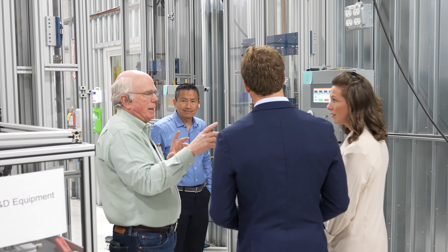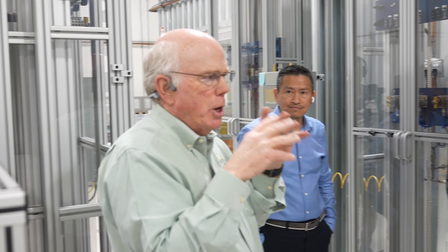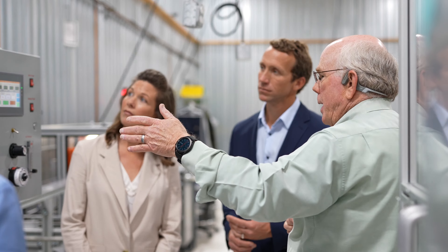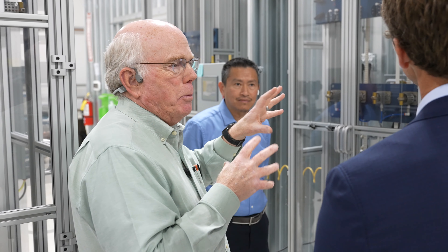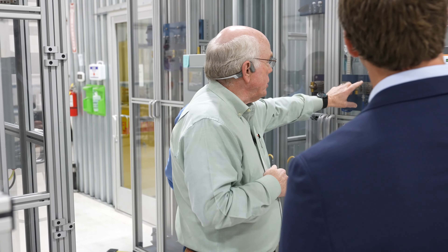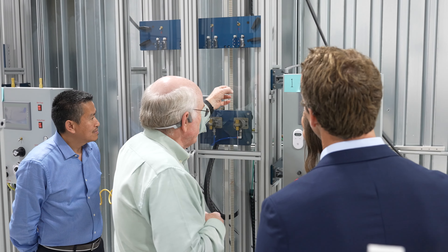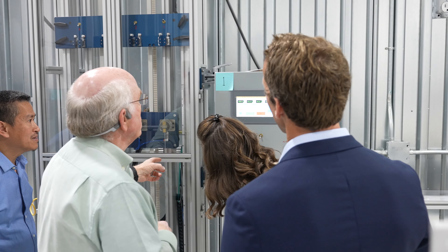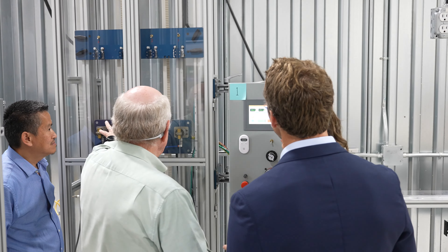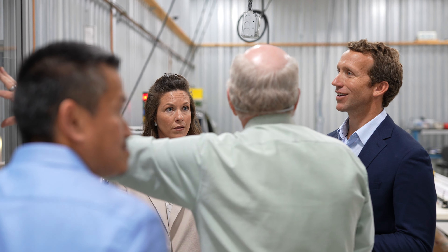The next step in making catheter shafts: after we have the braid onto a shaft with what's called a liner — there's an inner polymer liner, a thin plastic tube — it comes over here and we do a lamination. This can be done in an oven, but we get much better control with this kind of heat process. You see the catheter shaft on a mandrel. This thing travels down — it has four stations and is moving and shrinking because we put a heat shrink layer over this, and this machine is shrinking the layer onto it. This is how catheter shafts are made around the world.